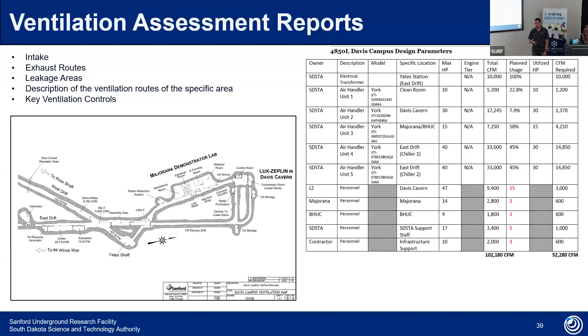It's kind of hard to see on this presentation, but there are 39 points, numbers correlating to the location, the time we're taking it, the temperature, the barometric pressure, the humidity, and the velocity. We calculate the CFM at that location, so we know what we're providing underground. It's kind of a health check for our ventilation system as a whole.